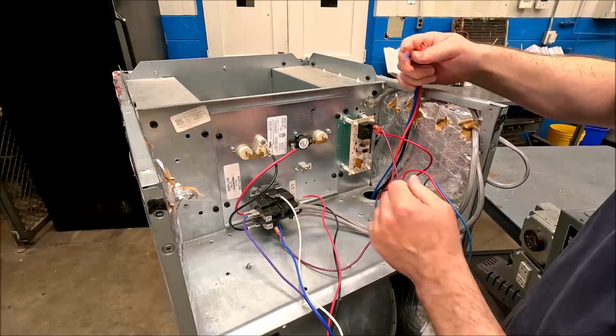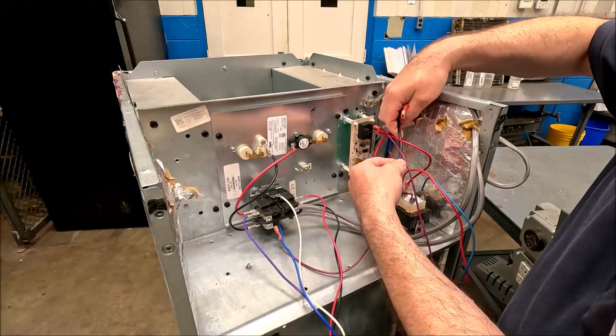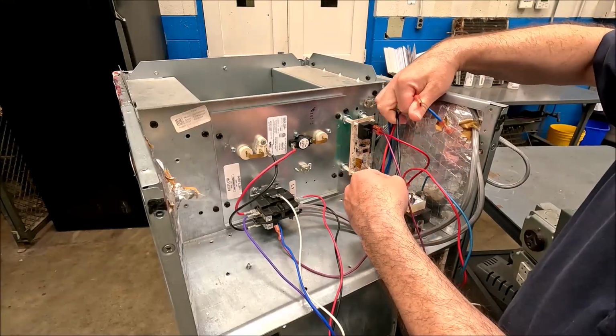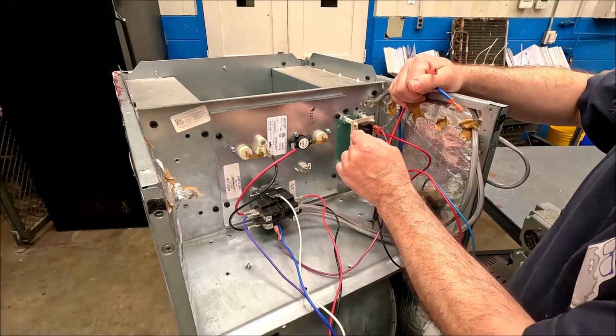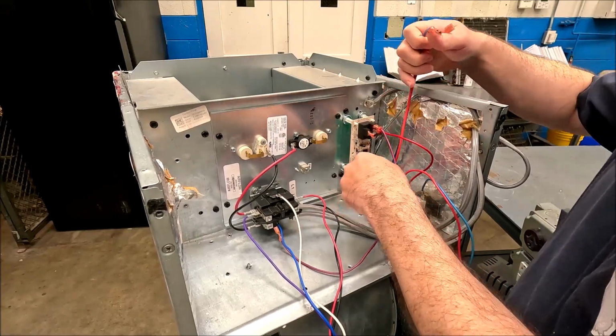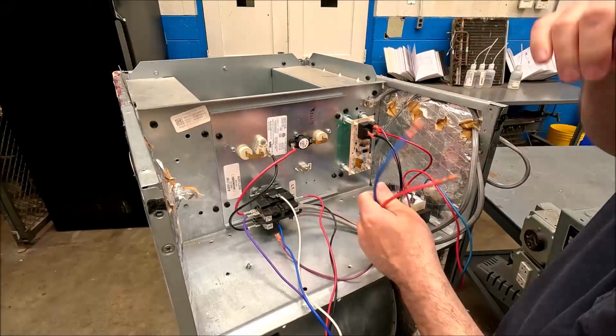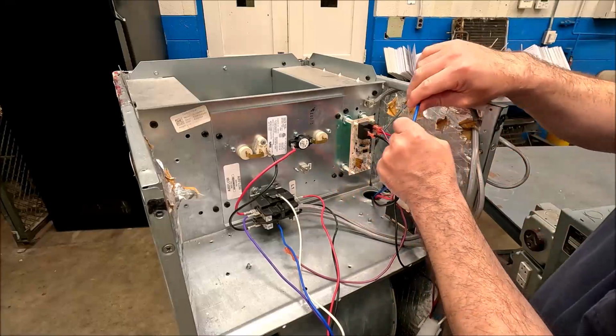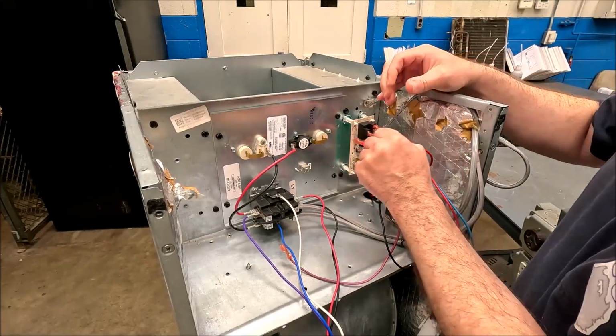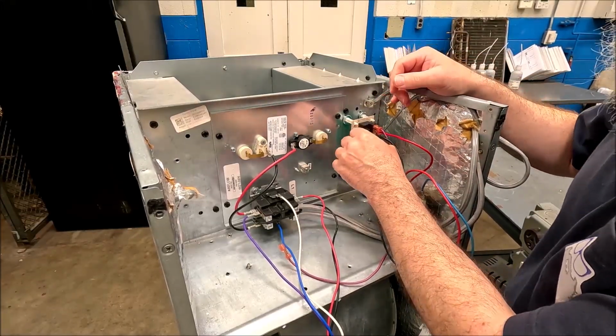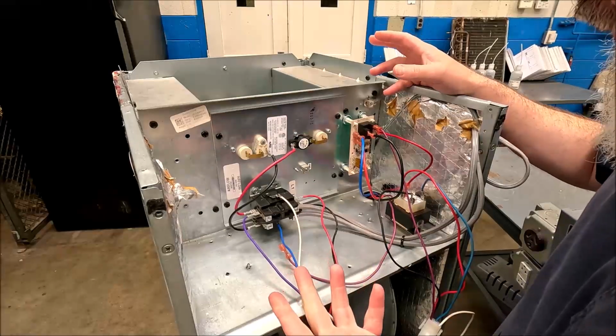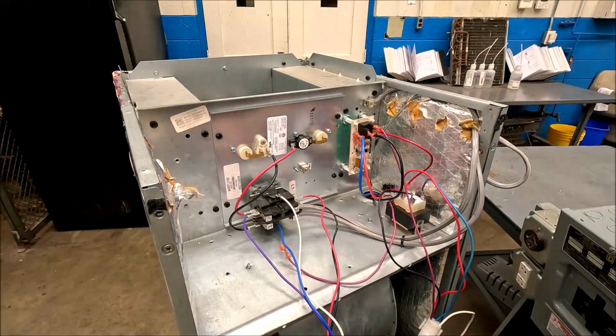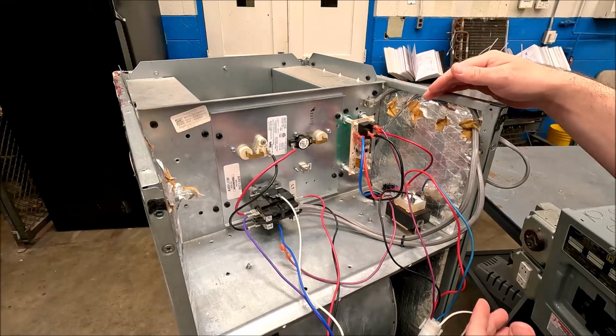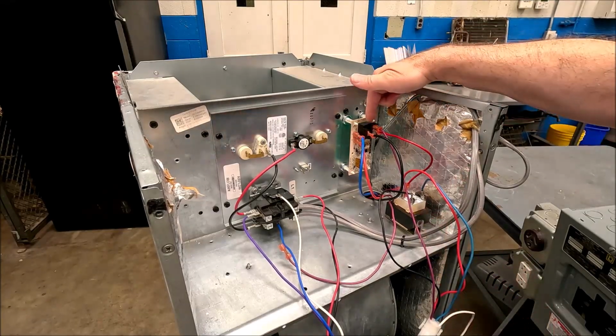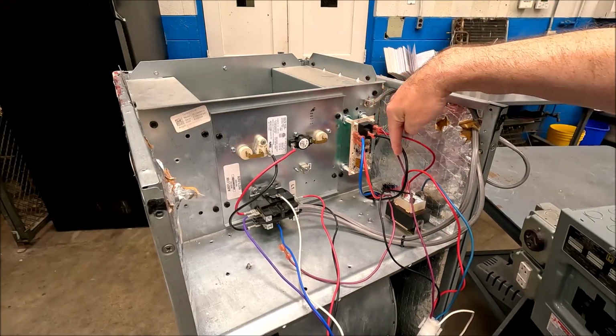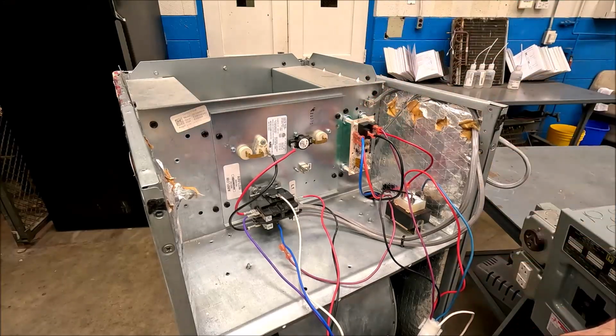I'm going to put this one on high speed, which is the black wire here for this PSC motor. I'm going to put that into the relay, and my other two unused speeds go on the M1, M2 of the blower board. I don't know why they chose M1, M2, maybe motor 1, motor 2, but those are dead terminals, they go nowhere. So that's power, control, the blower motor would be the load, and then we have to return back.